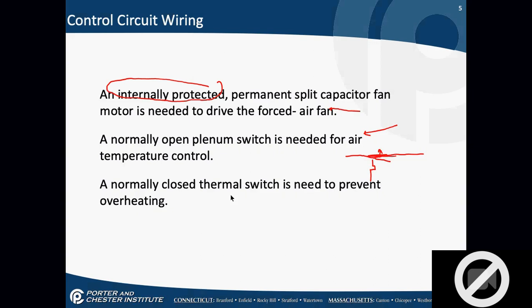We have a normally closed thermal switch again to prevent overheating. This is our high limit switch. So I'm going to have the normally closed high limit switch. That's going to open if the temperature gets too hot, and that's a closed switch. So as the temperature goes up, that's going to open if the temperature gets too hot. This is to prevent the furnace from overheating. We're going to talk a little bit more about this in the fan limit part of our conversation today. Any question on these three components? Because we've sort of talked about them already.